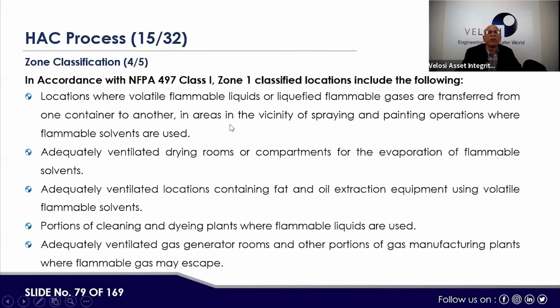If I go through the locations where volatile flammable liquids or liquefied flammable gases are transferred from one container to another, in the vicinity of spraying and painting operations where flammable solvents are used, this is called Class 1, Zone 1. Adequately ventilated drying rooms or compartments for the evaporation of flammable solvents. Adequately ventilated locations containing fat and oil extraction equipment using volatile flammable solvents. Portions of cleaning and dyeing plants where flammable liquids are used. Adequately ventilated gas generator rooms and other portions of gas manufacturing plants where flammable gas may escape.